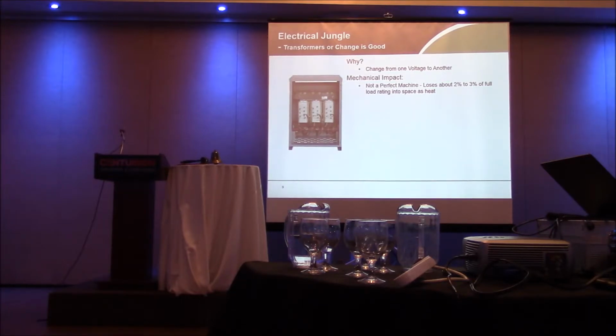So what that means is, if you have a large load and you're trying to supply it at a low voltage, besides the fact that I'm going to have to use big conductors, because I have to make the conductor bigger to carry more current - the power equation we were dealing with in the first place - as you increase the voltage, I can get away with less current. If you reduce the voltage for the same power, I have to increase the current, and every time I increase the current, I've got to make the conductors bigger.